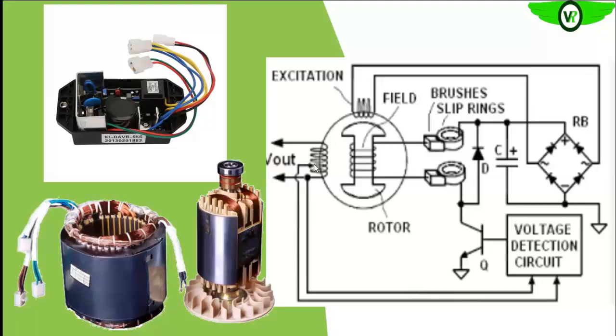So if it is not enough, it will adjust the amount of DC voltage that will be coming from the AVR, from this terminal to the main field, to raise the magnetization and thus the amount of voltage that will be induced in the generator, the main armature.